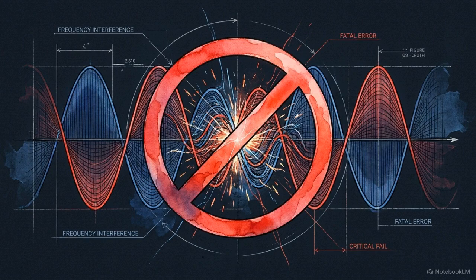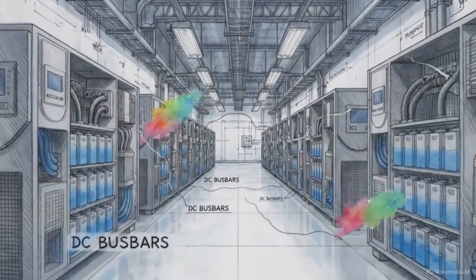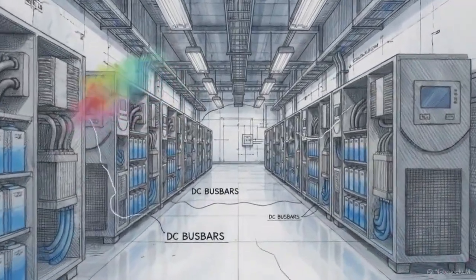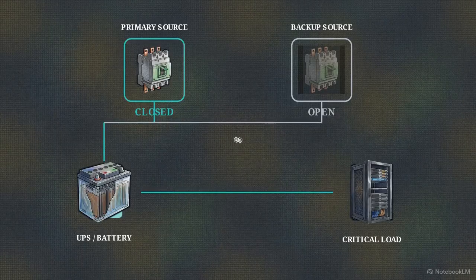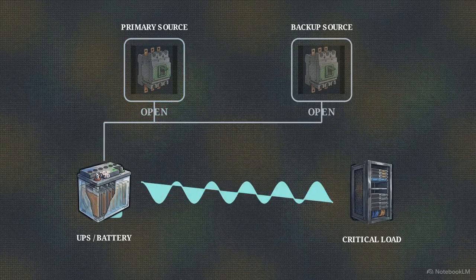The ATS enforces a controlled, transient blackout. The critical load only survives this intentional blackout because the uninterruptible power supply, the UPS, bridges the gap. The instant incoming power drops, the UPS discharges its internal batteries, maintaining a flawless sine wave to the server floor while the mechanical breakers transition.